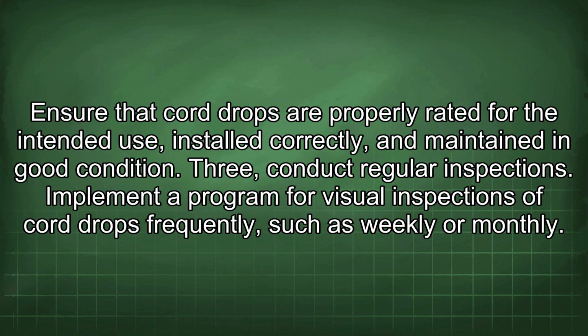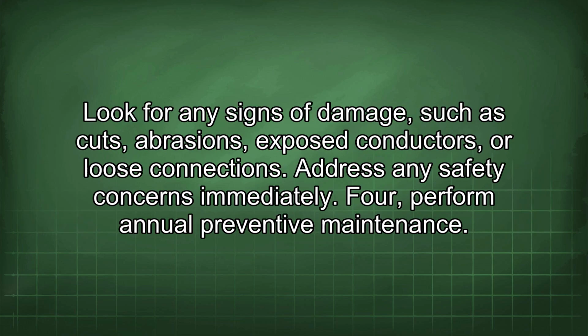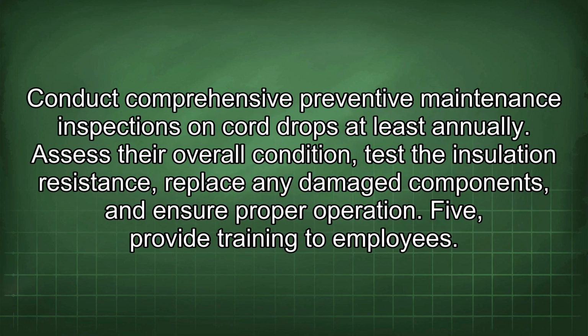3. Conduct regular inspections. Implement a program for visual inspections of cord drops frequently, such as weekly or monthly. Look for any signs of damage such as cuts, abrasions, exposed conductors, or loose connections. Address any safety concerns immediately. 4. Perform annual preventive maintenance. Conduct comprehensive preventive maintenance inspections on cord drops at least annually. Assess their overall condition, test the insulation resistance, replace any damaged components, and ensure proper operation.